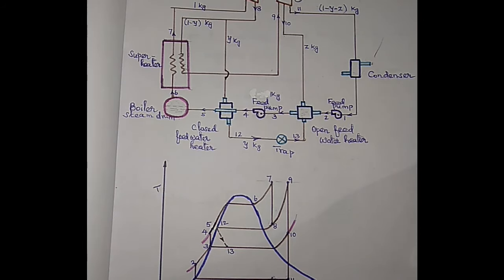At high pressure, where the high temperature is maintained, the water will hold less gas, so deaerating will be better when the open feed water heater is used at a higher pressure range.